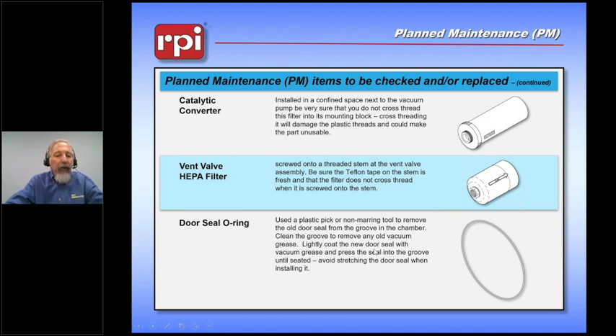We have a door O-ring seal. You want to pull the door ring out carefully. There is a plastic pick available to get it out. When you get the O-ring out, make sure you clean the door ring gasket, the door gasket ring, to make sure that there's nothing going to block the new gasket from going in. We do recommend that you lightly coat the gasket, pressing the ring into the groove in the door until it's completely seated. Try to avoid stretching the door seal when installing it.